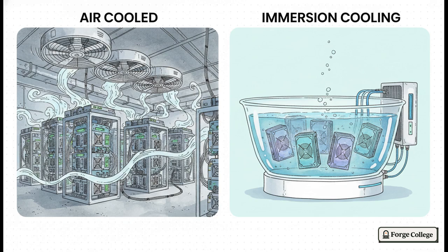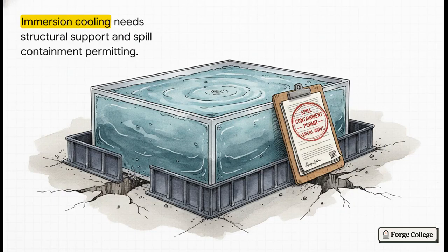On the complete opposite end of the spectrum, we have immersion cooling, and this is exactly what it sounds like. You are literally submerging your incredibly expensive heavy computers into a high-tech bathtub filled with a specialized, non-conductive dielectric fluid. I know, it sounds totally crazy, but it works brilliantly. It's virtually silent, lets you pack machines way tighter together, and drops your PUE down to an incredibly efficient 1.03 to 1.08.